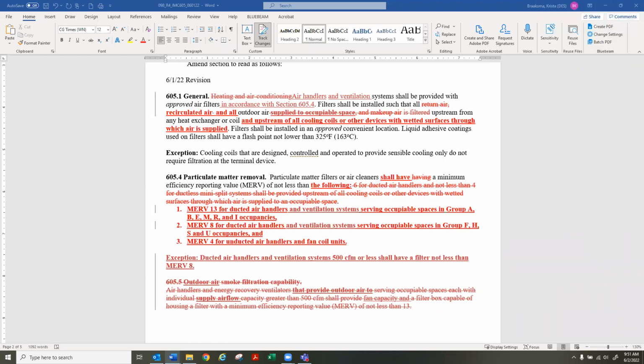Yeah, just to talk to that a little bit. The 500 CFM is going to limit most small residential units, so we're not going to see a scenario like this where the ERV is going to require that MERV 13 or the fan coil. That 500 CFM is really getting into larger spaces where there's going to be lots of outside air and lots of recirculated air through the fan coil. And so there's two different types of filtration we're trying to achieve: outside air filtration for smoke and all other outside air contaminants, and the potential contamination inside the space. So having two MERV 13 filtration is a much bigger benefit on these larger systems. So I would say it's worth not having that clarification to have only one filter that's a MERV 13.